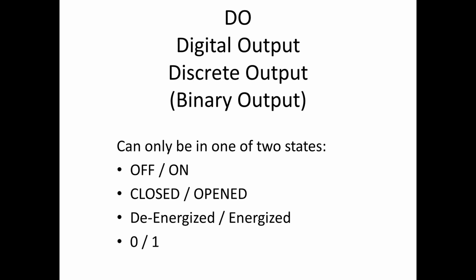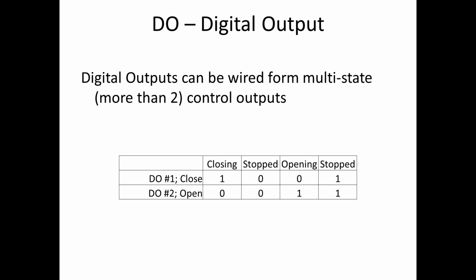I'm going to skip right over the digital input or digital output because it's the same thing as the digital in. This is what is getting information taken in. Digital out is information going out. So the digital input is the valve or the equipment telling you what it is. The digital out may be the PLC telling the pieces of equipment what status it wants to go to. If you're sending a digital out, you may be telling a valve to open, or you may be telling a pump to turn on. So that's what the digital output does. It does the same thing as input, either on or off, open or closed.